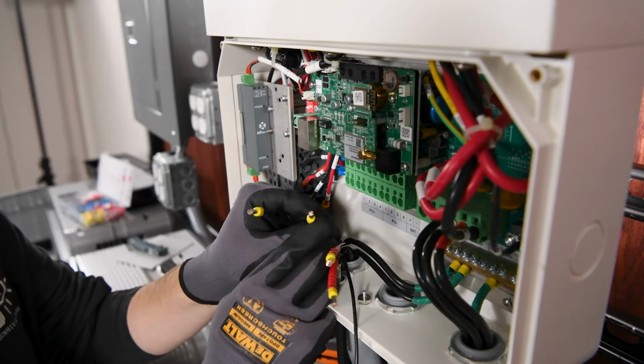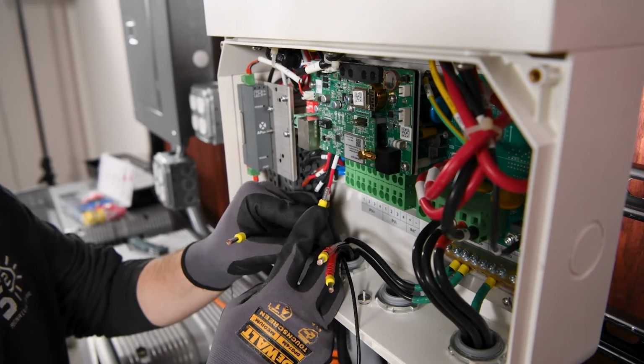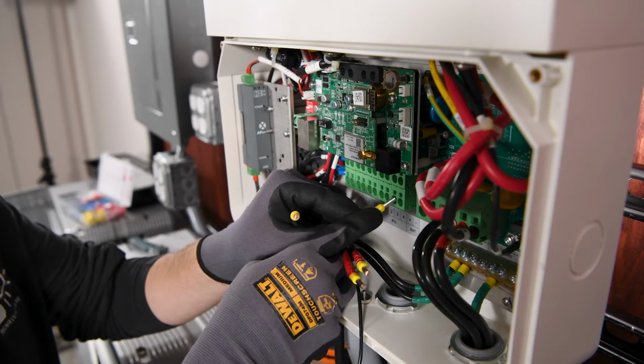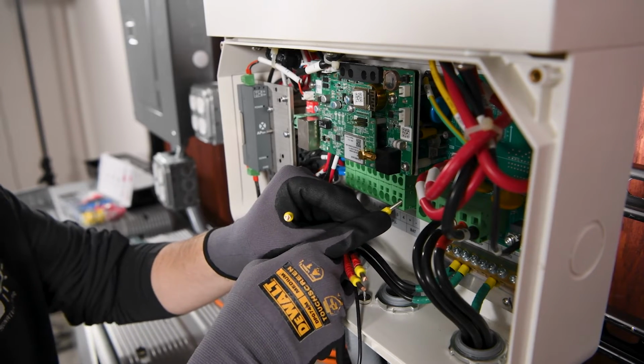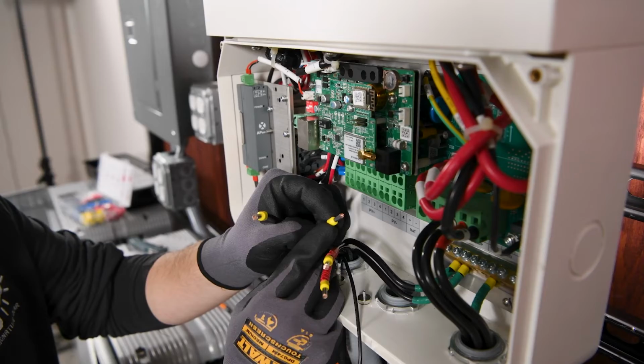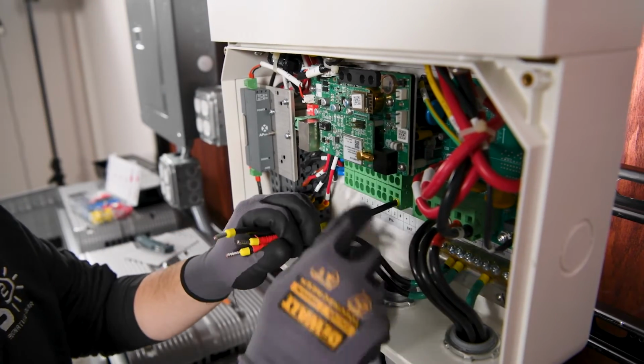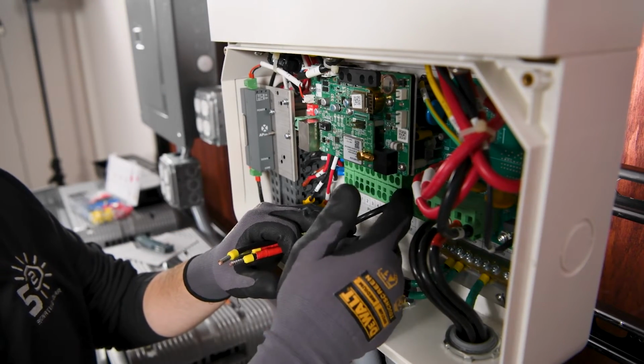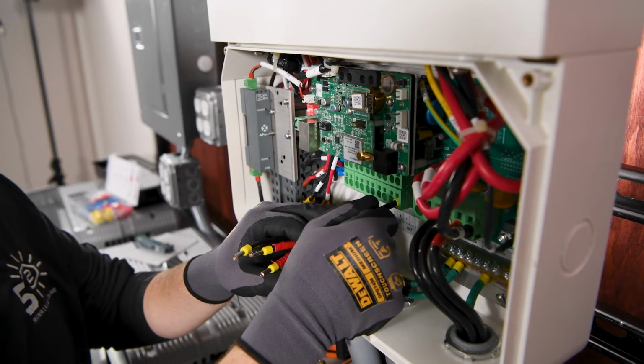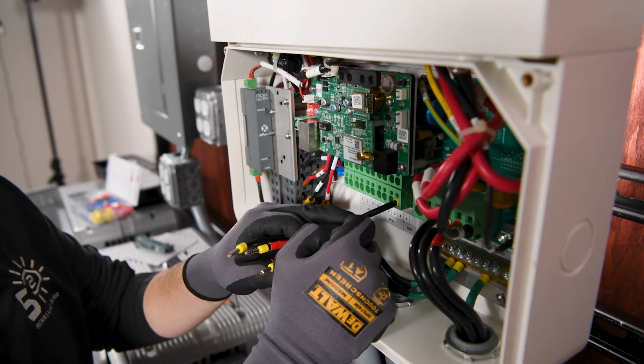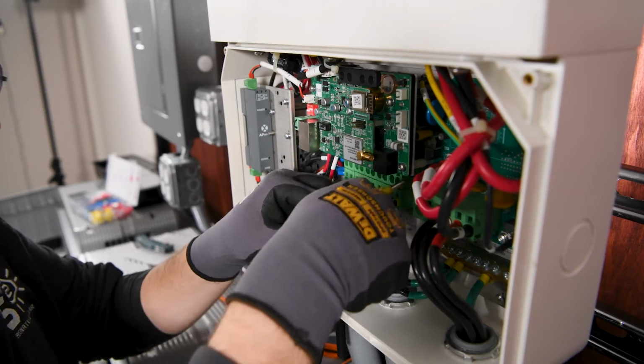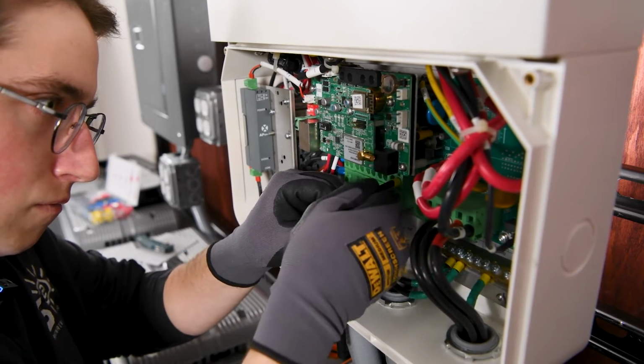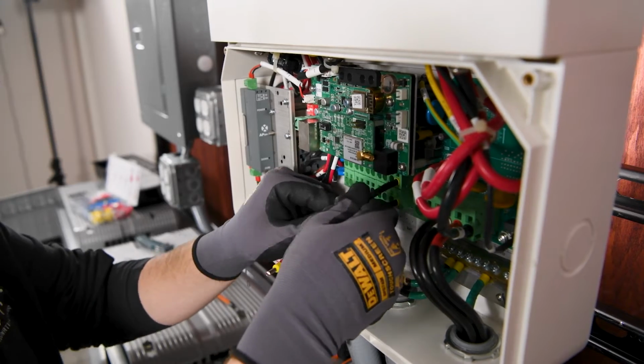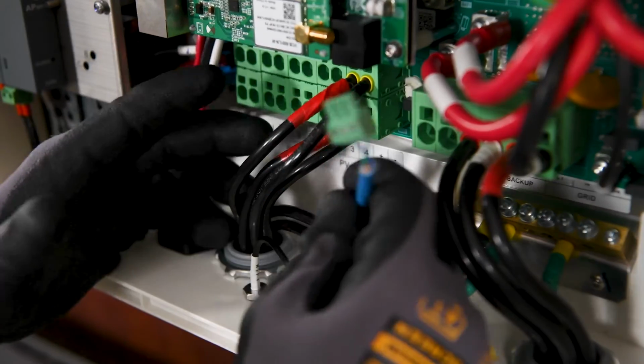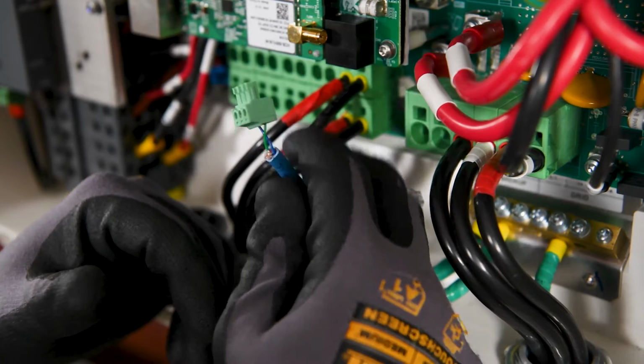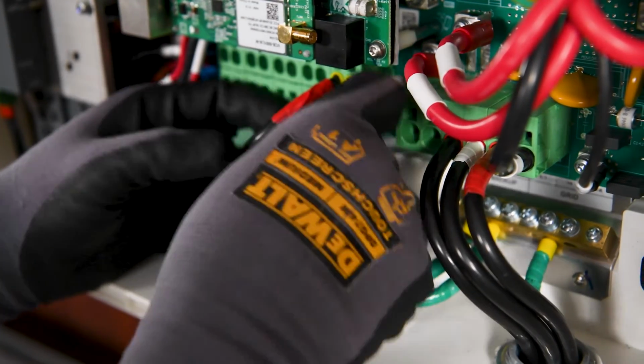This is very similar to how they were connected on the connection points or our output from the 11.4 Growatt inverter. Just insert them into the terminal port here and just push in firmly. Once you push in firmly, the jaws or the teeth in the back of the port will grab the conductor. Just give it a slight tug to ensure that it's seated properly. With our battery cables connected, we're going to reattach our communication cables here.